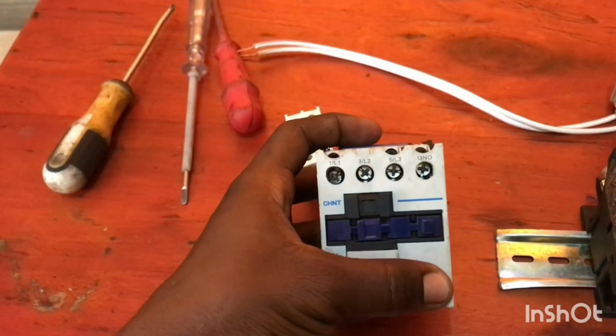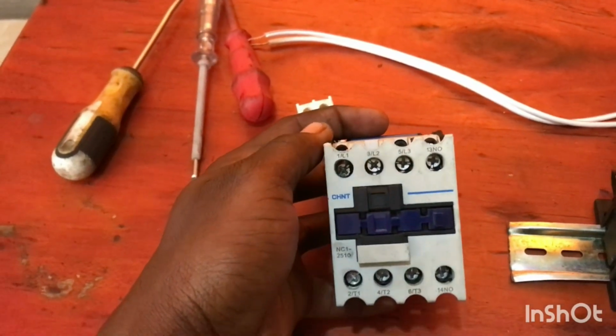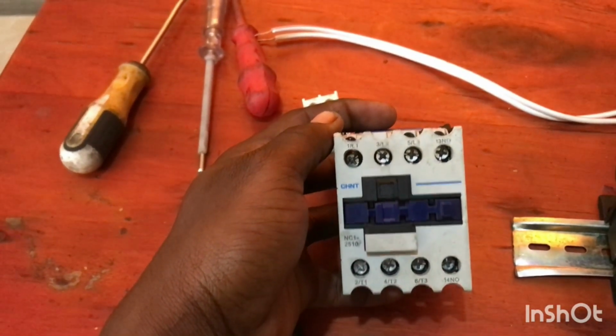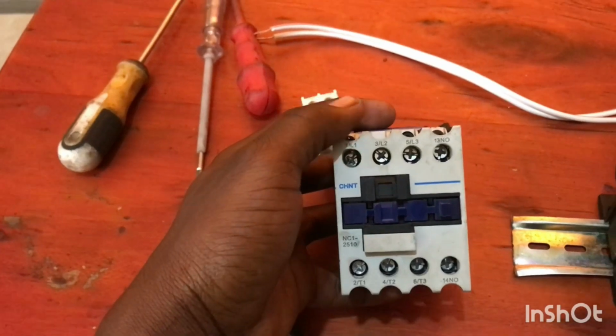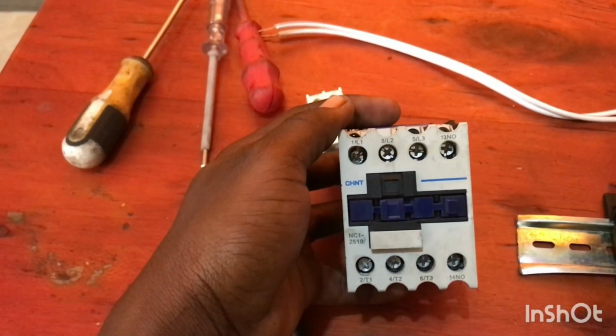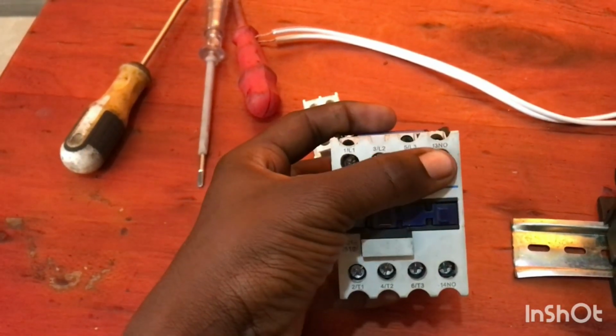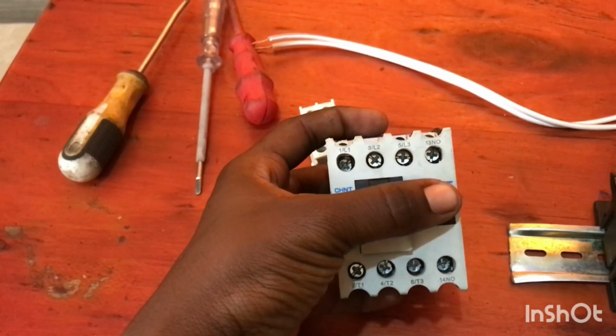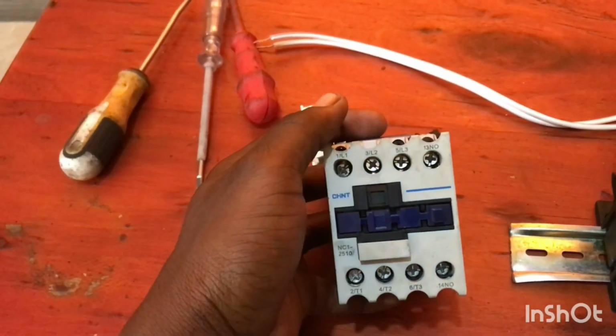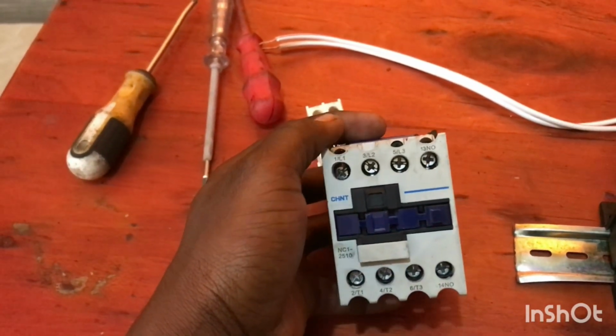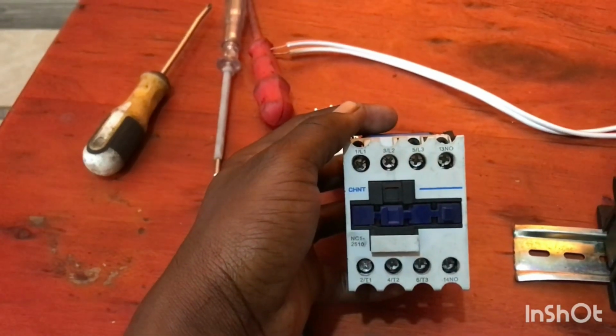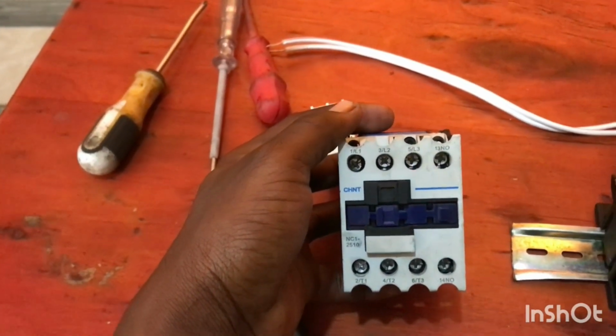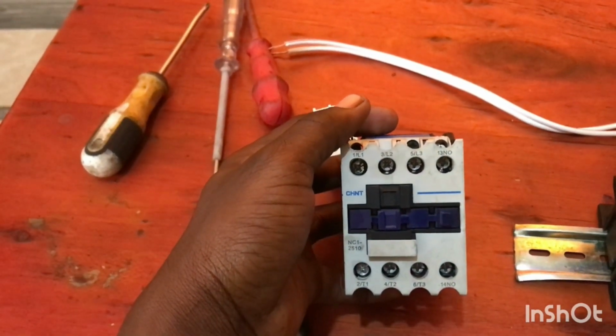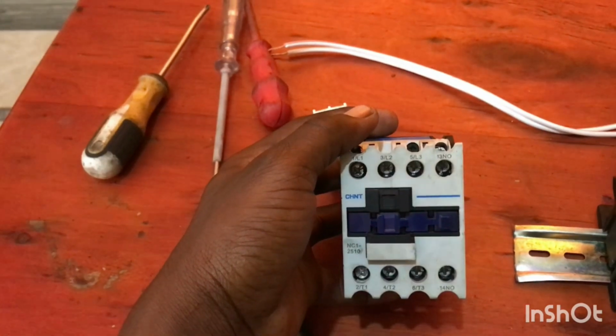But for normally open, it means when it is at rest, there is no power from point A to point B. But when it gets energized, the normally open will close, meaning there will be power from point A going down to point B at 14. So this is all we have to know about a contactor.